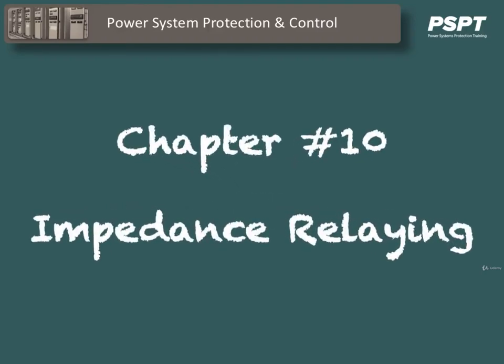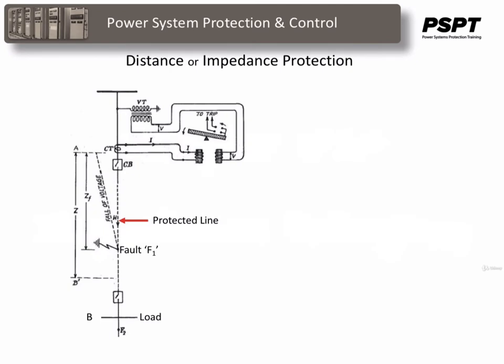Chapter 10: Impedance Relaying. Distance relays are double actuating quantity relays with one coil, the restraining coil, energized by voltage, which by virtue of being connected to a PT or VT is proportional to the line voltage at the relay location. The other coil, the operating coil, is energized by current, proportional due to its connection to a CT, to the line current at the relay location.